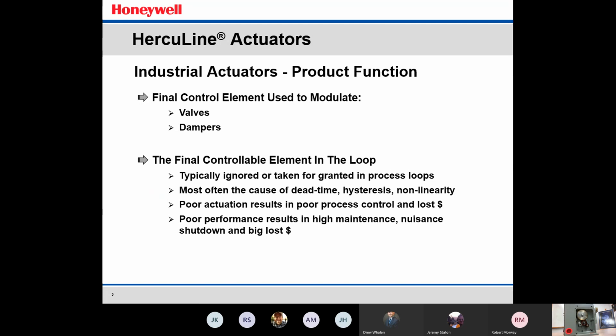So the industrial actuators, typically these are used on modulating systems, on valves and dampers. They are the final control element in the control loop. So as you all know, in a control loop, you have your sensor, your PID controller, and your final control element, which is your actuator. And the actuator, or the final control element, plays a very key role in the PID loop. This is what gives you the accuracy of your control, allows for reduced dead time hysteresis, and allows sometimes for cost savings based on how good or poor the control is. So those are just a couple examples where they're used in valves and dampers.